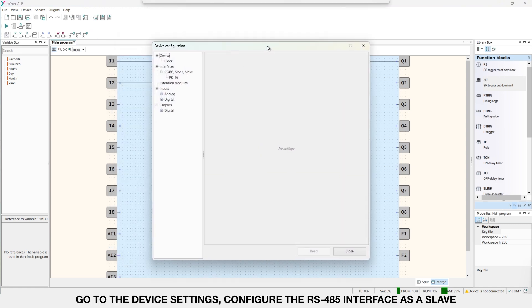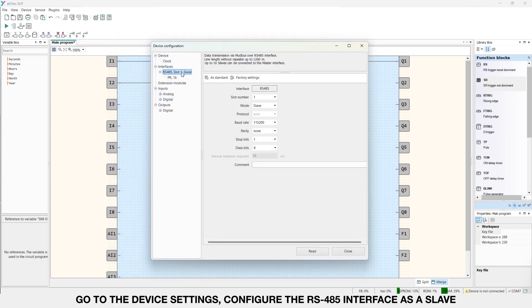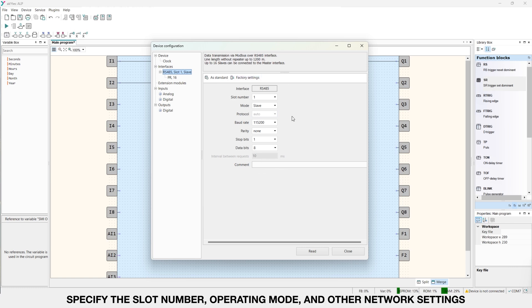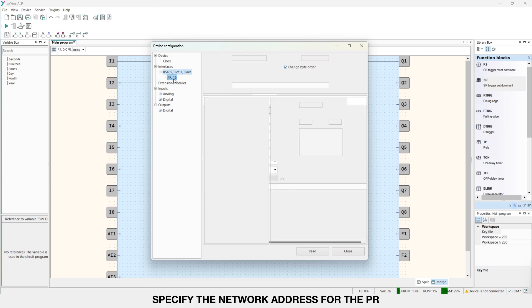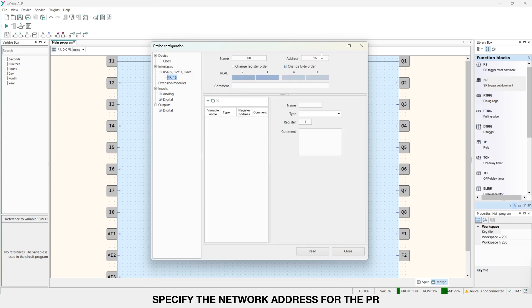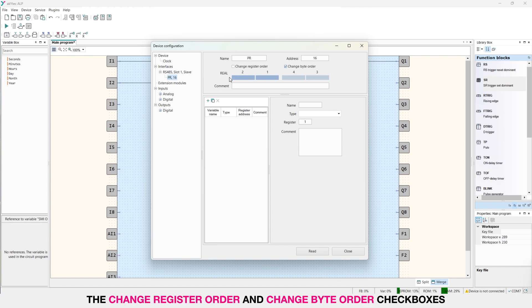Go to the device settings. Configure the RS485 interface as a slave. Specify the slot number, operating mode and other network settings. I will leave them as default. Specify the network address to the PR. Since we won't be transmitting data of type real, we won't touch the change register order and change byte order checkboxes. And since PR is a slave device, they won't affect anything.